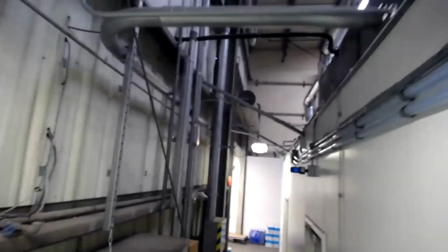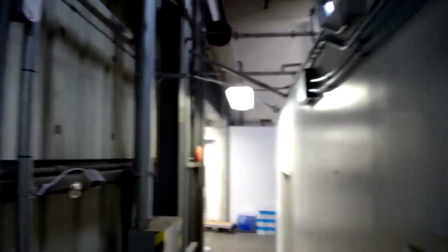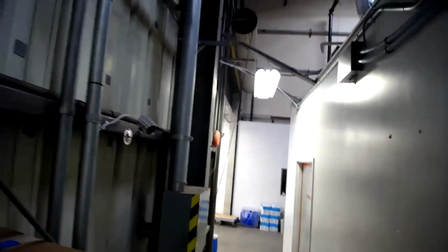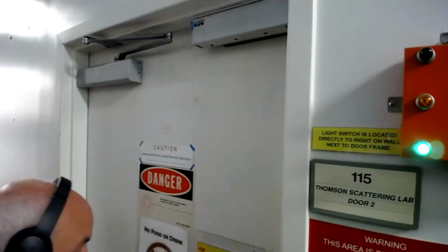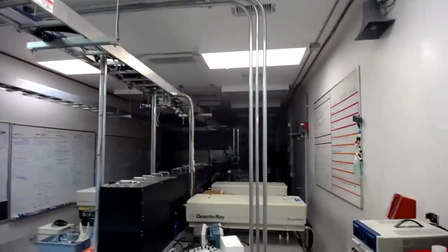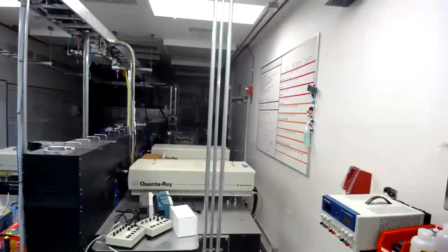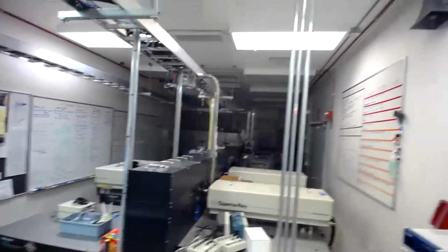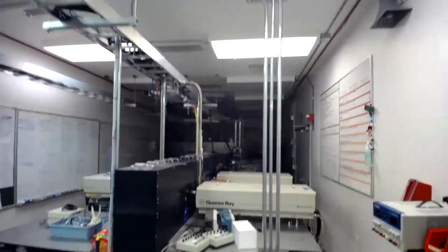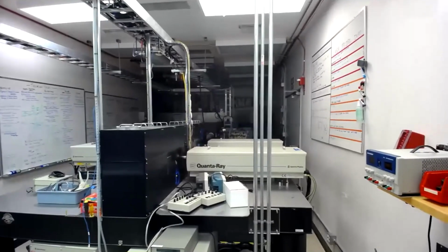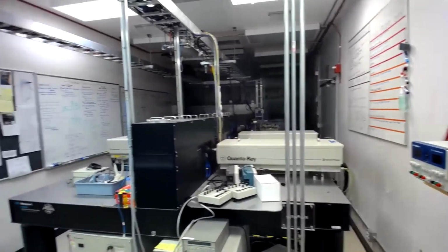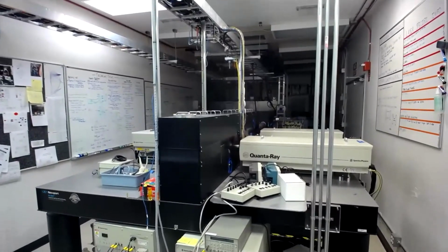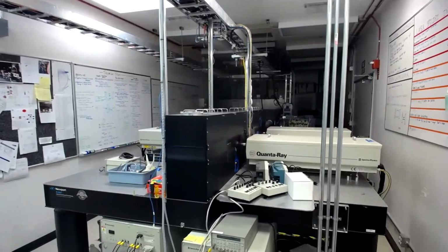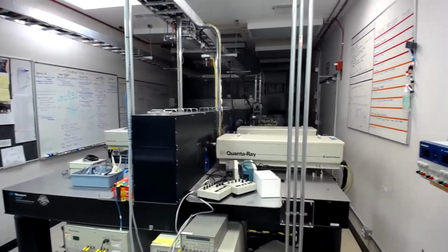Now, just to show you, that was an electrical engineering area, and that's kind of dusty and dirty. Let me see if I can get into one of our premier optics labs and show you how nice and clean. It's air conditioned, it's well lighted, except back there where the lights are off. This is a Thomson scattering lab. And we have 10 very high-powered lasers that we can fire into the machine. The light scatters off the electrons in the machine, and then we detect that scattered light. And from that, we can find out what the temperature and pressure is in the machine. So this is one way we can measure temperature and pressure in the plasma.